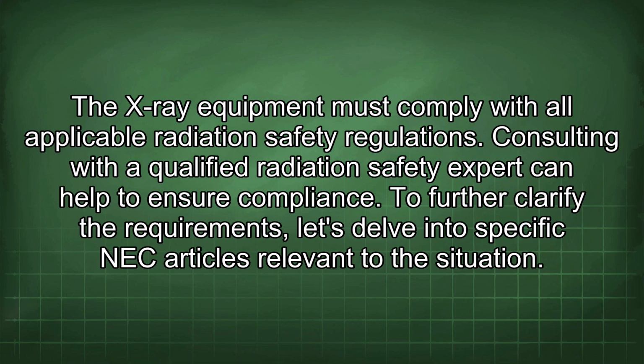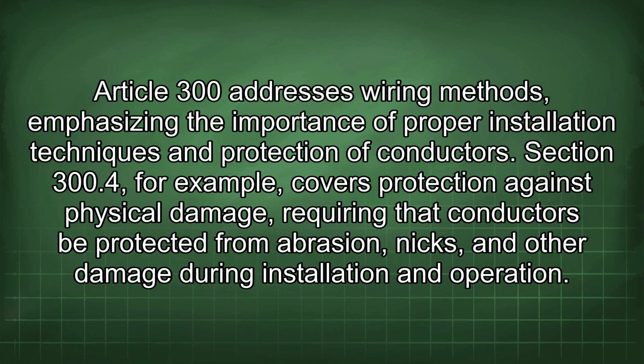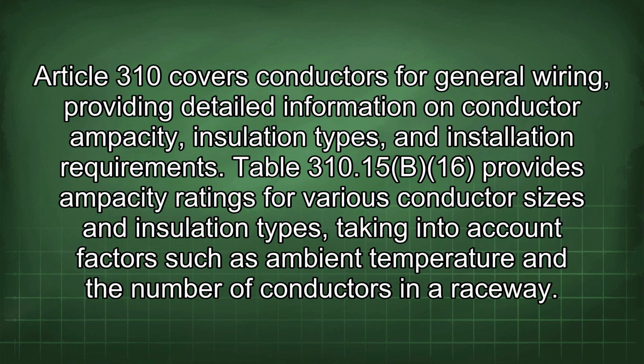To further clarify the requirements, let's delve into specific NEC articles relevant to the situation. Article 300 addresses wiring methods, emphasizing the importance of proper installation techniques and protection of conductors. Section 300.4, for example, covers protection against physical damage, requiring that conductors be protected from abrasion, nicks, and other damage during installation and operation. Article 310 covers conductors for general wiring, providing detailed information on conductor ampacity, insulation types, and installation requirements. Table 310.15(B)(16) provides ampacity ratings for various conductor sizes and insulation types, taking into account factors such as ambient temperature and the number of conductors in a raceway.